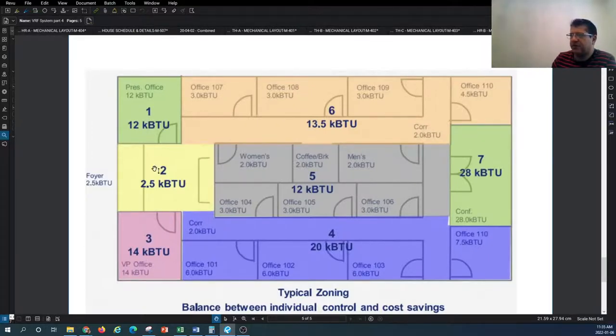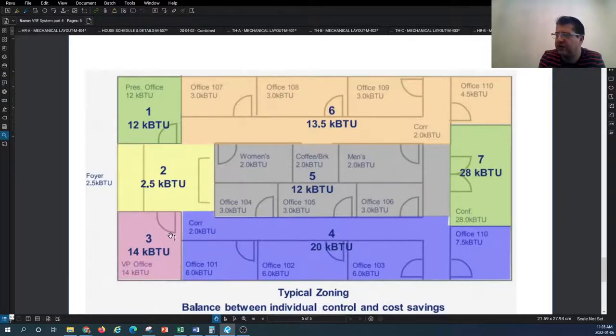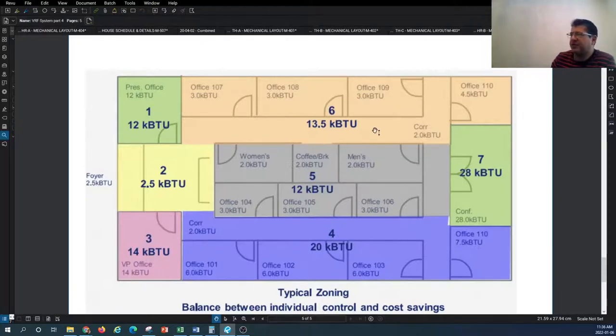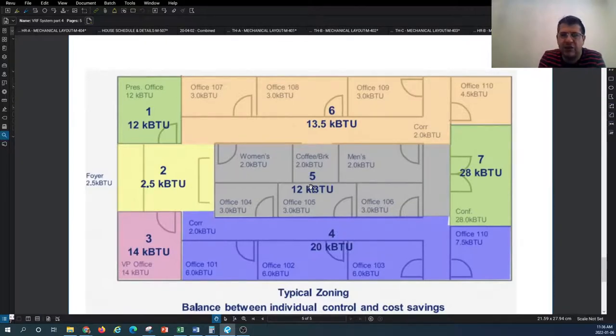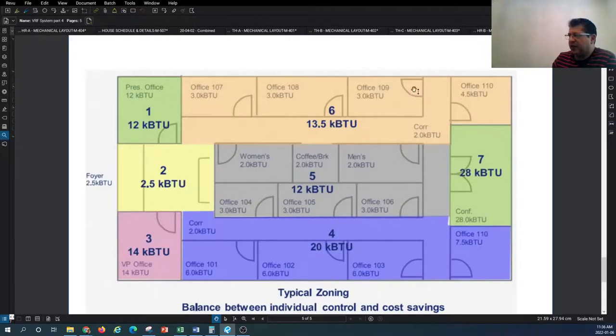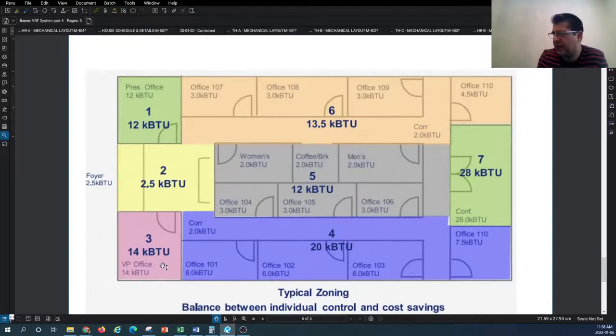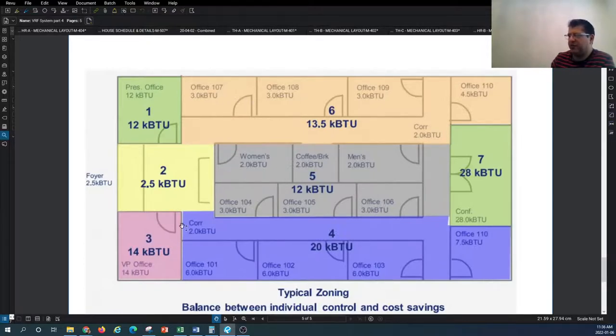In the seven-zone option, the corner zones — zones one, two, and three — are separated because they are adjacent to exterior walls, have windows, and experience different heat transfer compared to interior spaces. Zone five, for example, is a core zone with no adjacent exterior wall and therefore minimal thermal heat transfer with the building envelope. The core is separated from the envelope zones, which creates a more balanced control approach.